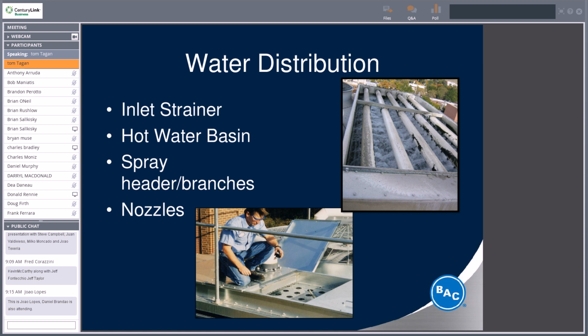The drawing or the photo down below is a gentleman on top of one of the Series 3000 towers that we just reviewed. He has taken the basin covers off and he's looking down at a hot water distribution basin. All of the black dots or the black circles, that's the top of the distribution nozzles. You can see he's got one in his hands. He's twisted it out to inspect it. So it's very important to keep your water distribution clean. Number one reason is for the efficiency of your cooling tower. But again, too, if you're operating during the winter season, even distribution is key, because if you don't get it, that's when you start to develop ice.